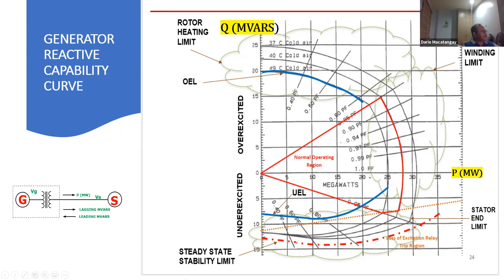So here on the left, you can see this is your sample generator, and this is your system, your transmission system. You see that you have a flow of megawatts and megavars. You need these megavars in order to maintain synchronism between the generator and the system. If you lose synchronism, you can damage the generator, the turbine, or you can cause problems to the system itself. So it needs to be synchronized, and you need that inductive power to maintain that synchronism.